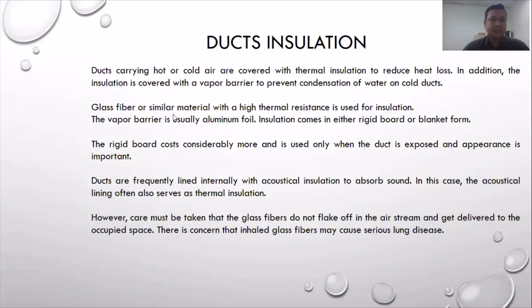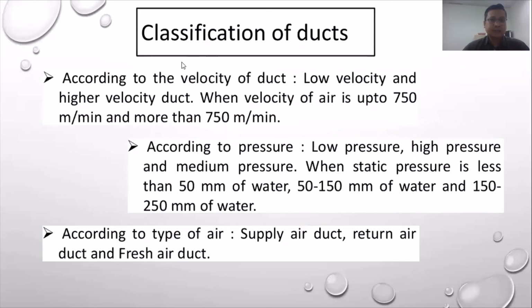This one is the type of material for the duct system. This one is the classification of duct, according to the velocity: low velocity, higher velocity duct systems. So up to 750 meters per minute is considered low, and above that higher. So low pressure, high pressure, and according to type: supply air duct, return air duct, and fresh air duct. So we separate by system, by supply, return, and the fresh air duct system.